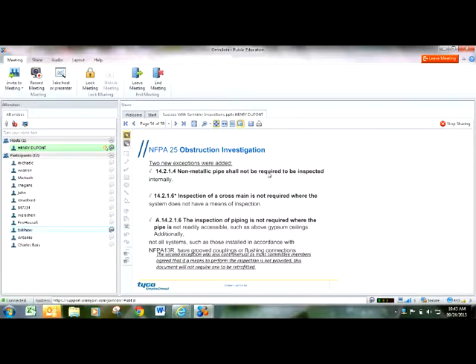I understand that. However, you can have foreign objects introduced into the sprinkler system, say from an underground fire main break. And I think the systems, whether they're plastic or steel, should be checked to make sure that there are no obstructions in the system. However, the new 2013 edition of NFPA 25 says plastic systems don't have to be inspected.